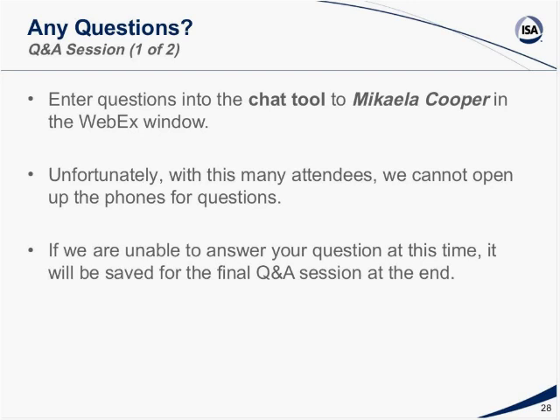All right, great, thanks. Our next question asks, what is the definition of a manual reset for ISA 84? Must it be in the field, or can it be done electronically in the control room? Typically expected to be done in the field. The reason for it to be done in the field is that the person goes out to the field device and makes sure they understand what caused the problem so that they can correct the problem and reset it locally. In other words, if it trips, it won't reset if the condition goes back to normal. The only way you can be sure of that is go out to the device.